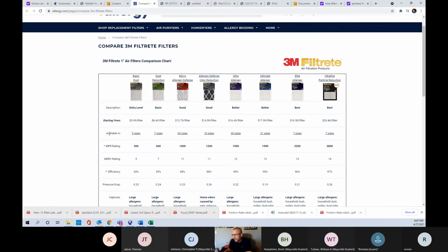So I hate them. If you had to have one for some reason, one thing you can do is increase the surface area. I don't have an example pulled up, but I have seen people put in even like 4-inch, probably more like 4-inch cabinets, but they'll increase the surface area across that coil to where they can put a bigger or wider filter than their ductwork.